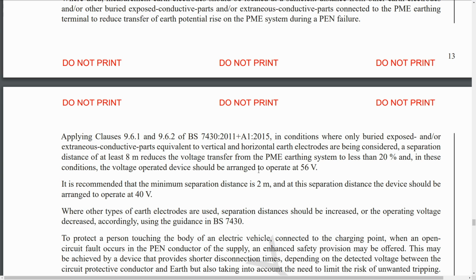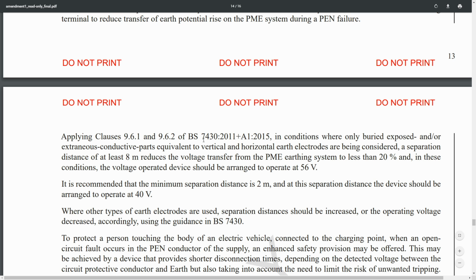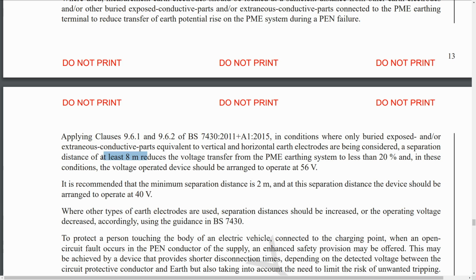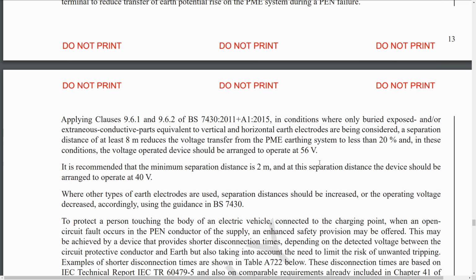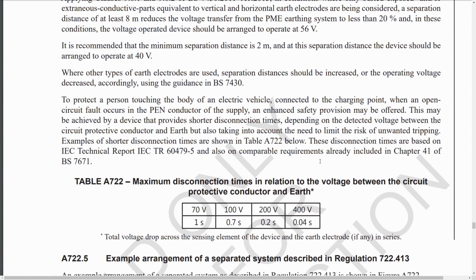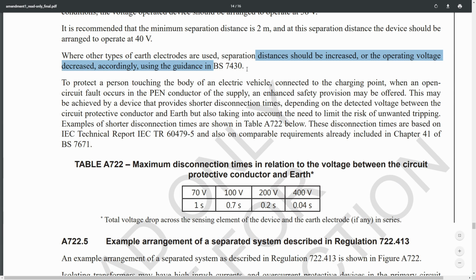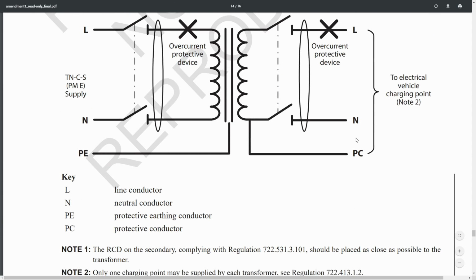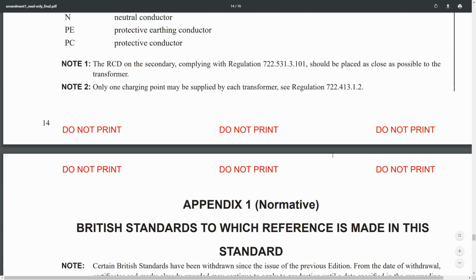But up here we've got clauses from a different standard, BS7430. A separation distance of at least 8 meters reduces the voltage transfer from the PME earthing system to less than 20%. So again, 8 meters away from any buried conductive items like metal pipes or cables or whatever, certainly in a domestic environment that is going to be pretty much impossible because a lot of houses aren't even as wide as 8 meters. So yeah, that's why just converting it to TT is often not going to be a particularly practical option. And say a bit of additional information there taken from that additional standard BS7430. The rest of this is pretty much as before, just some examples of a separated system there.